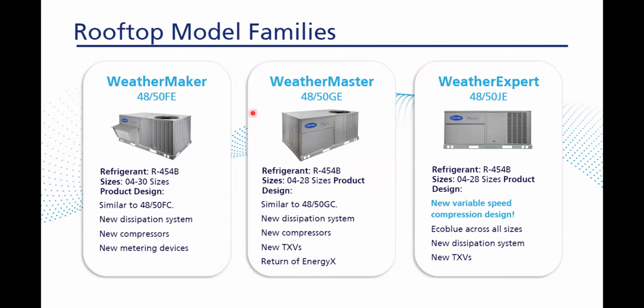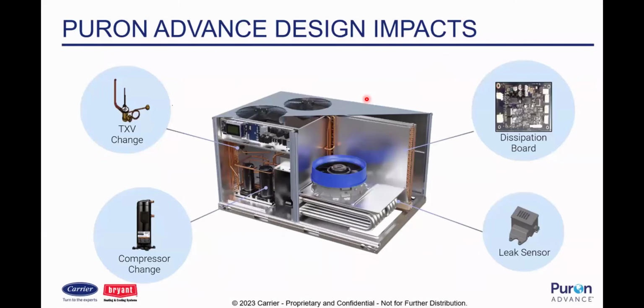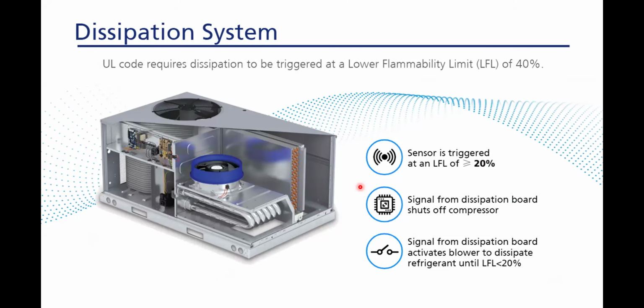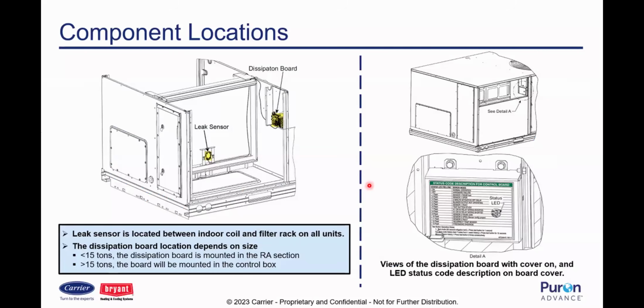Rooftops also changing, as I mentioned. The digits change. You know, if you guys are used to a 48FC, now it's a 48FE. The GC becomes a GE, right? Different TXVs, dissipation controls, same kind of control board as we had before, leak sensor still tripping at 20% lower flame limit. Everything's exactly the same as the other stuff we talked about. The one weird thing on rooftops I want to point out is that if the rooftop is less than 15 tons, the leak board will be found in the return air section. If it's more than 15 tons, it'll be in the control enclosure. Obviously, it belongs in the control enclosure. It's just there's no more space on a small unit.